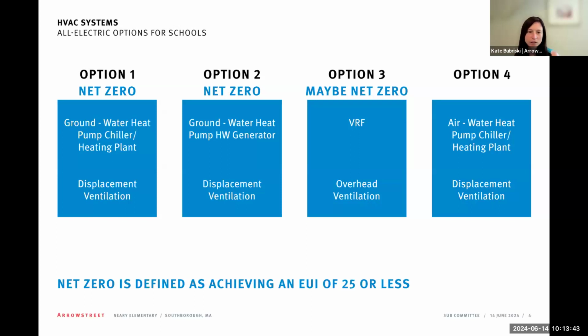And so, that being not the lowest cost construction wise or lowest cost after incentives, it's actually one of the most expensive systems now. Plus the fact that once you're in operations, because it is a gas boiler system, you'll be dependent on the utility and utility costs and fluctuation, as opposed to if it was an all electric building, you potentially can have solar either on site or through some other process that can help you stabilize and have predictable costs of utilities. And so we typically don't recommend gas systems for school buildings at this time.